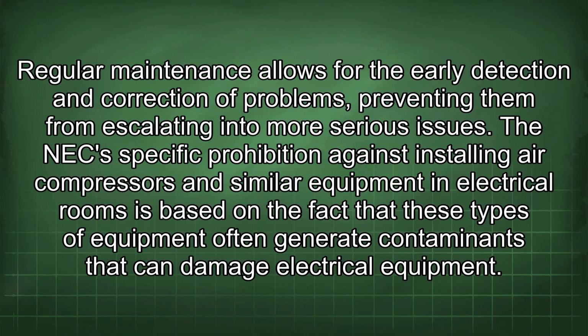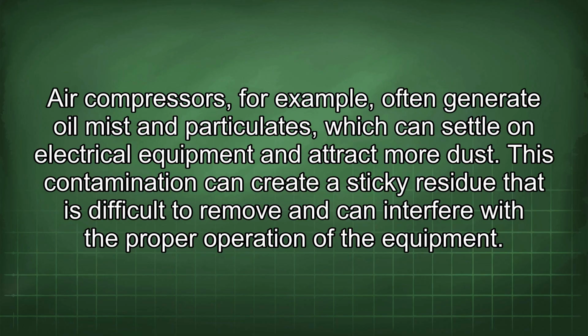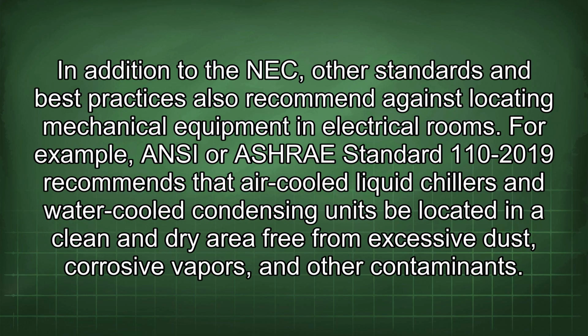The NEC's specific prohibition against installing air compressors and similar equipment in electrical rooms is based on the fact that these types of equipment often generate contaminants that can damage electrical equipment. Air compressors, for example, often generate oil mist and particulates, which can settle on electrical equipment and attract more dust. This contamination can create a sticky residue that is difficult to remove and can interfere with the proper operation of the equipment.